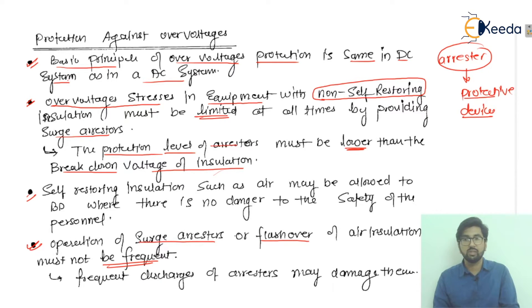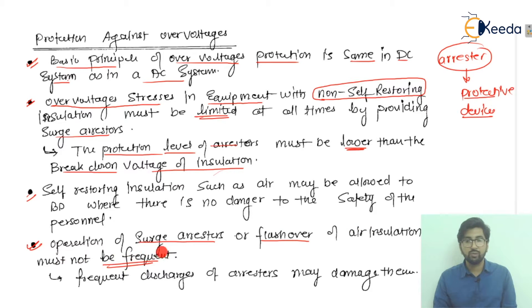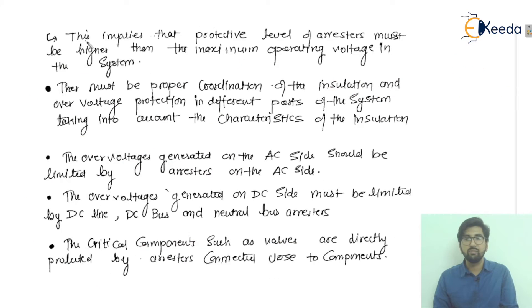The flashover of air insulation must not be frequent. Frequent discharges of the arrestors may damage the system, and this implies that the protective level of the arrestors must be higher than the maximum operating voltage in the system.